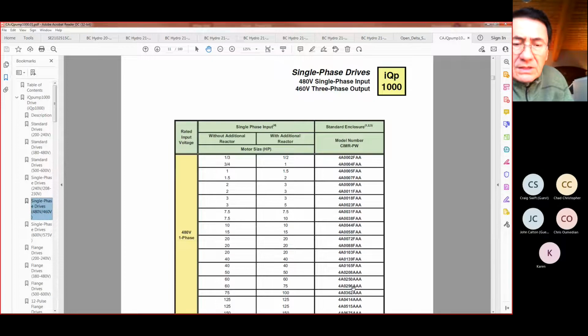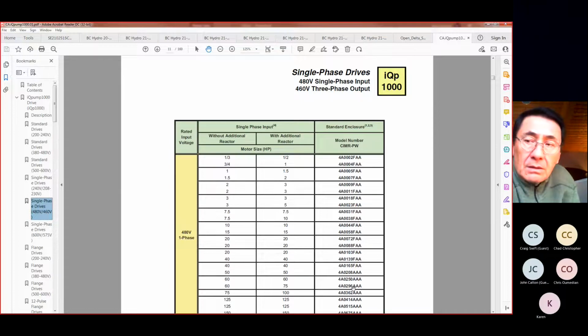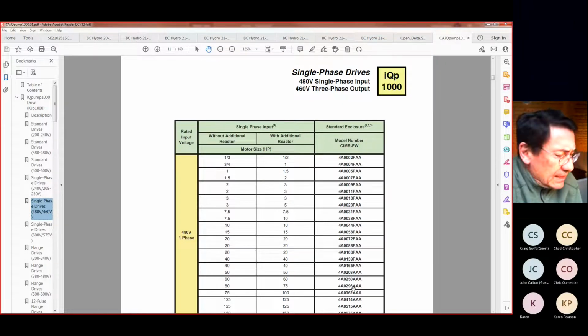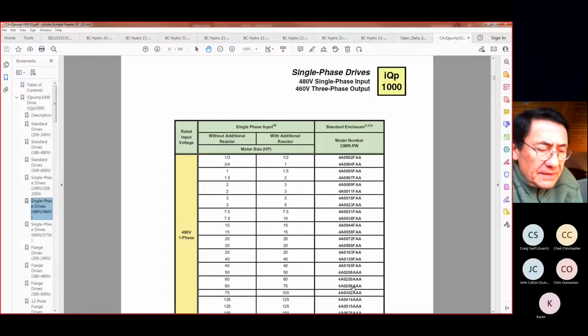Therefore, this leads to a catastrophic failure, as opposed to the mantra that we try to hold in our design, which is fault trip before component failure. Because we do not have the sensor, we cannot fault trip. That's why this situation is much more severe, and it is very important to comply with the guidelines that Yaskawa gives you for these various unbalanced power supplies. I will say that if we treat open delta as a single phase and size up severely, then we're safe.